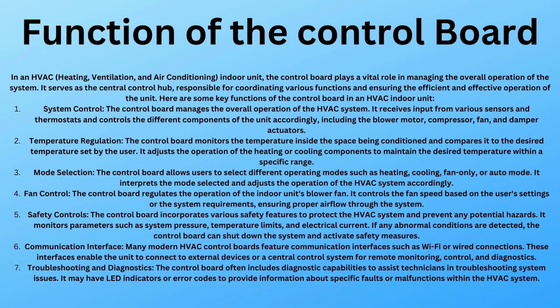In an HVAC (heating, ventilation, and air conditioning) indoor unit, the control board plays a vital role of managing the overall operations of the system. It serves as a central control hub, and that's what I was talking about. This is the brain of the system, responsible for coordinating various functions, ensuring the efficient and effective operation of the unit. Here are some key functions of the control board in an HVAC indoor unit. And the control board is in the indoor unit. It's not on the wall or outside. It's fundamentally inside your gas furnace or your air handler.